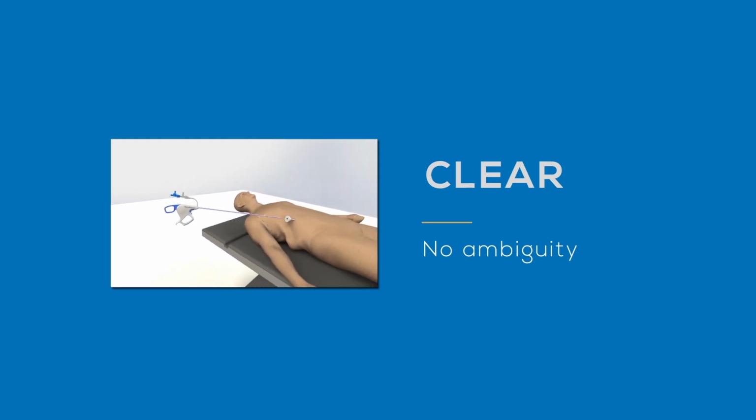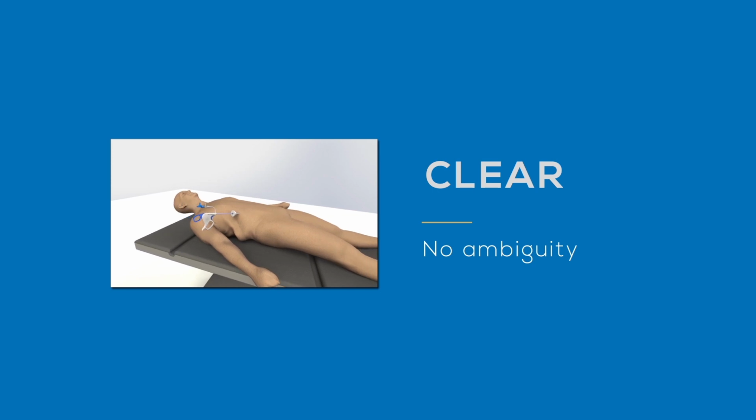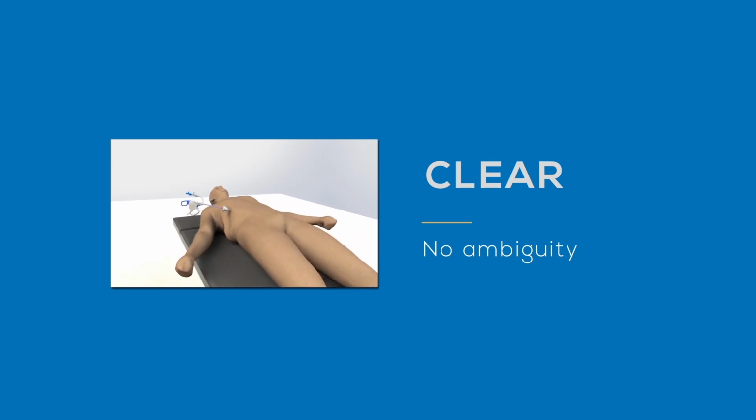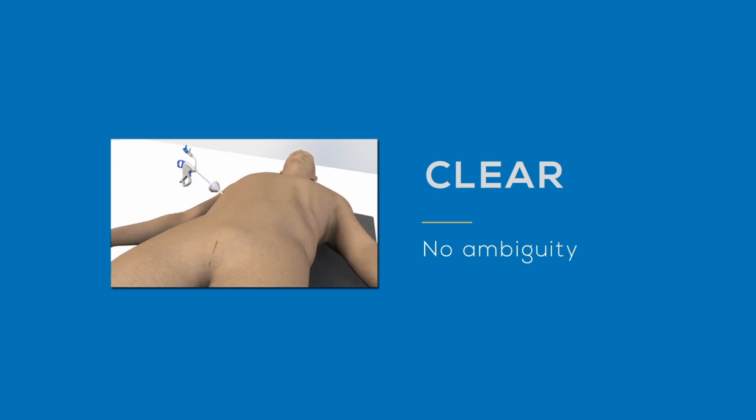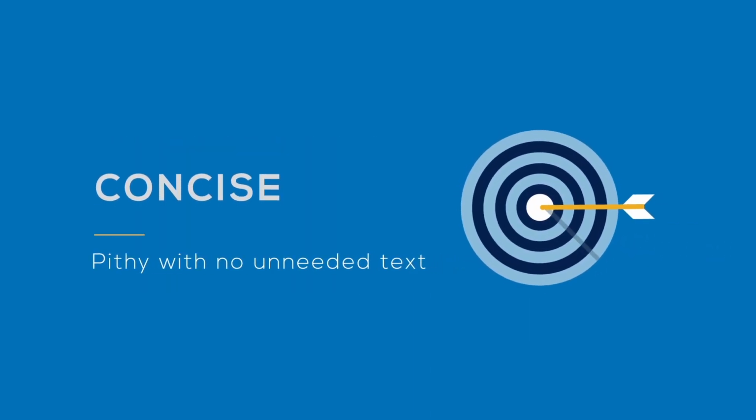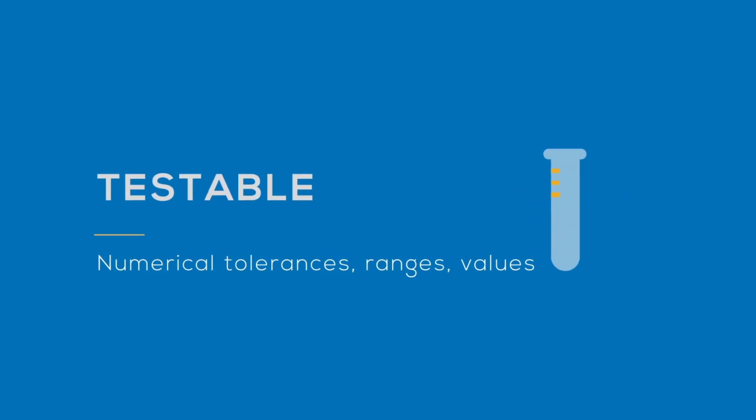into a product. For secure retract, the device needs to be delivered through a 5mm trocar, which is one of the smaller port sizes used in laparoscopic surgery. The wording in the description should be concise. Try not to bury the description in unnecessary text, but use simple, short statements. Any quantitative limits, tolerances, ranges, and intended values should be indicated when possible.